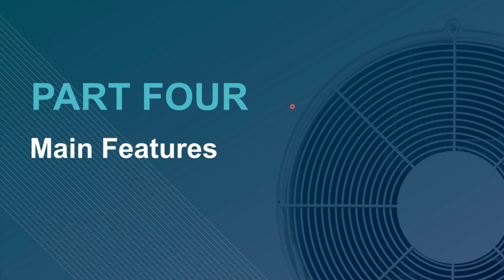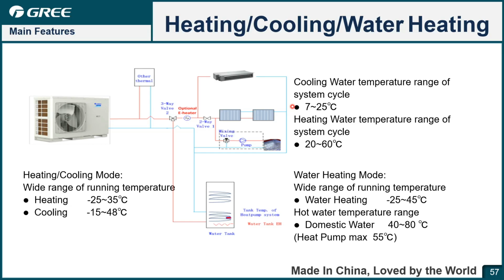So the next part is the functions and features of the VERSATI 3. For the VERSATI 3, the operation range and water temperature range is very wide. So for heating mode and cooling mode, here is the ambient range: for heating, -25 to 35 degrees Celsius. For cooling, it is -15 to 48 degrees Celsius. You can see it's very wide. For most of the countries, it's okay. And for the cooling water, from 7 to 25 degrees Celsius. For the heating water, 20 to 60 degrees Celsius.